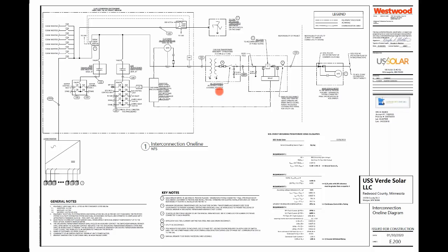With our switchboard file, we can do up to 1000 volts under UL 891, but realistically, most UL circuit breakers max out at around 690 volts. So you're not going to typically see a UL installation up to 1000 volts yet. It is certainly within the works of the major equipment suppliers to get to that level, but typically 600 volts is going to be the maximum AC you're going to see in one of these switchboards. And 600 volt is what they seem to now design most of these systems to. Correct. Yep. Versus a couple of years ago where 480 volt was common design. Correct. Yep. So we are pushing it.